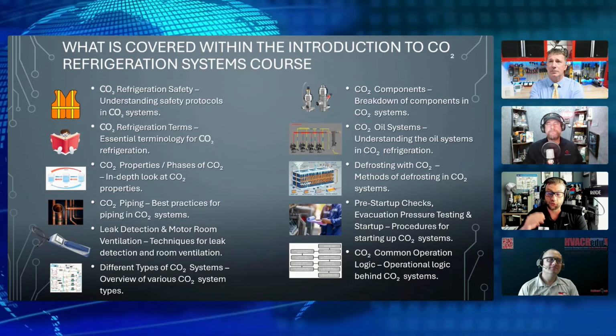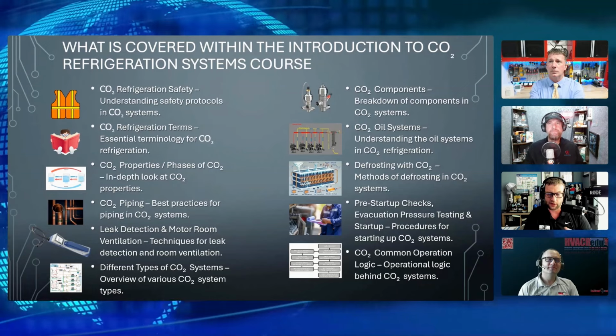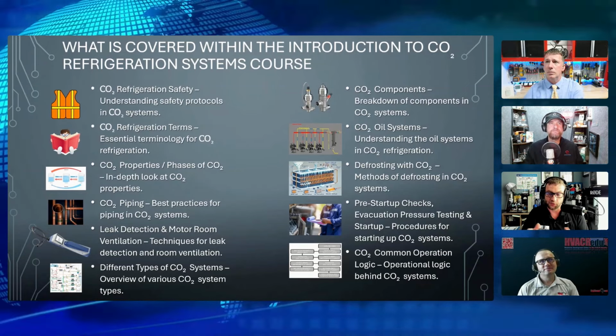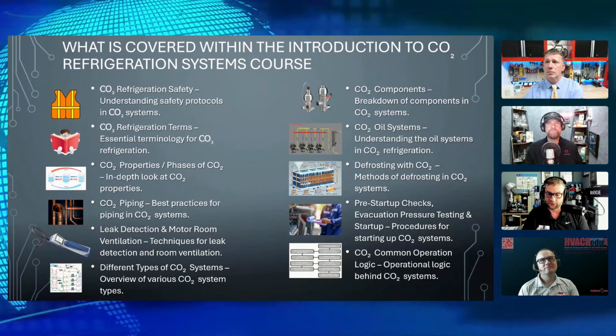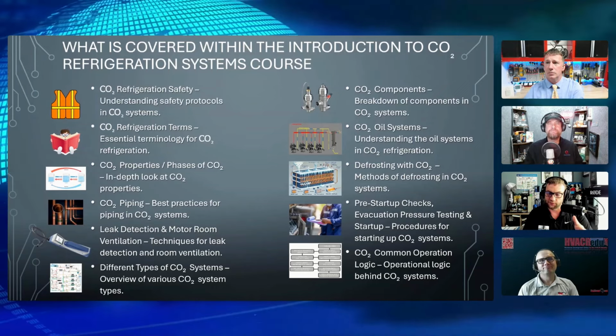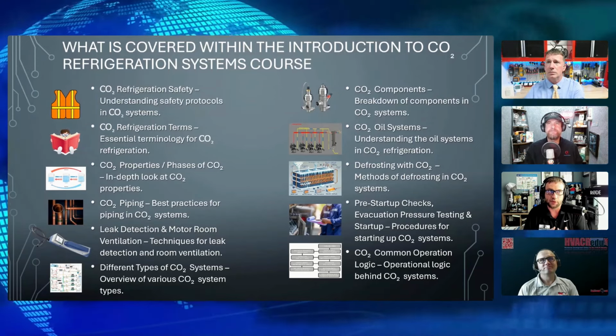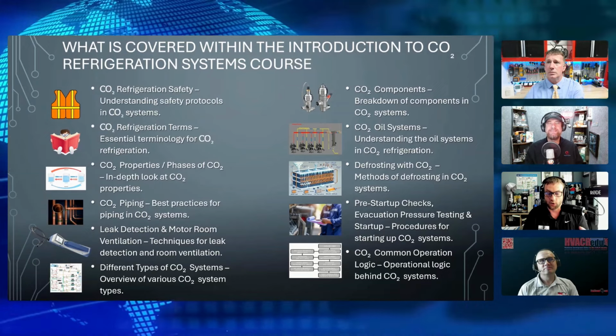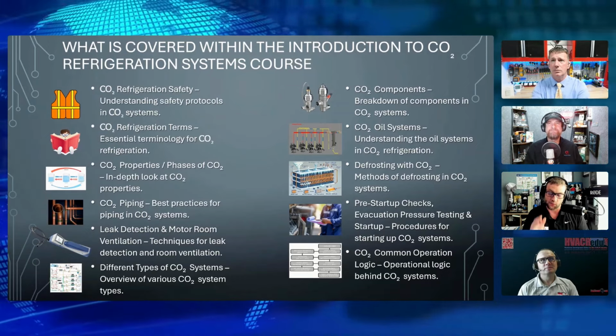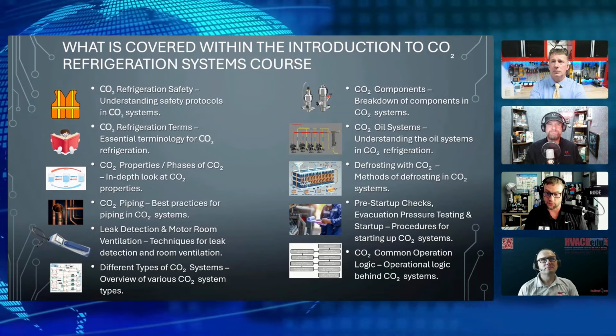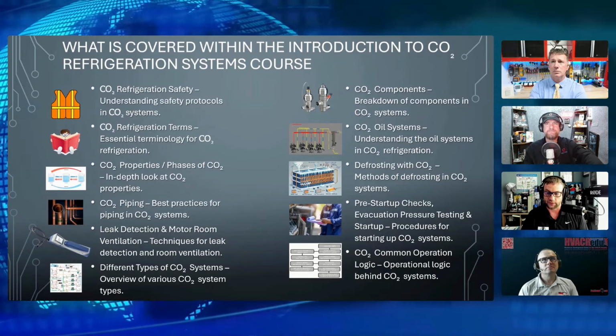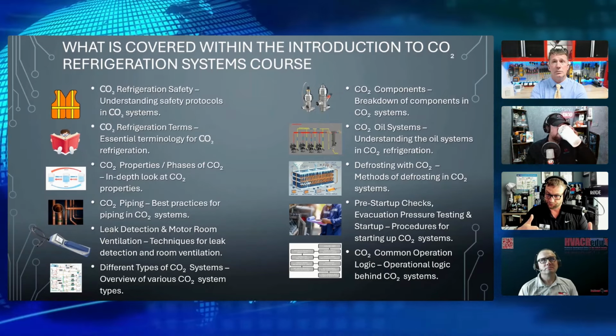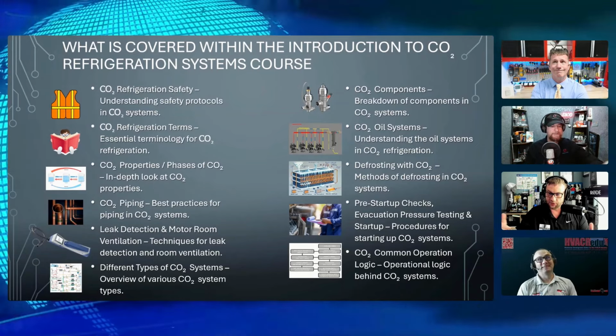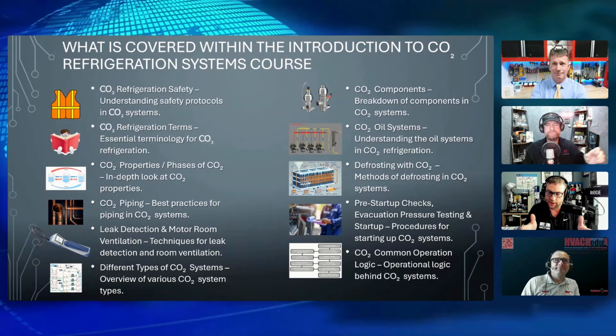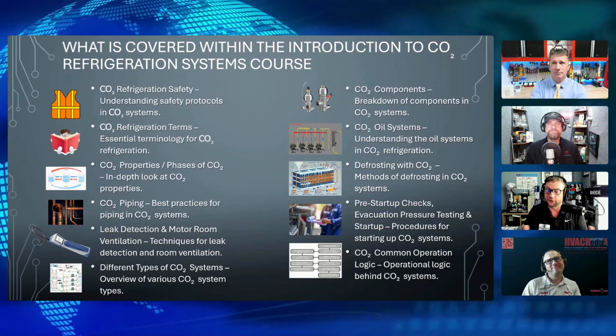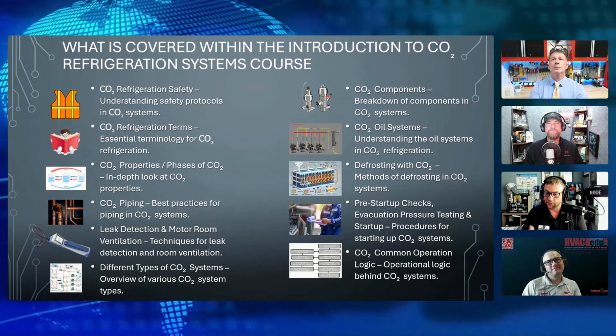So the way the piping is, which I didn't really discuss the other parts of the piping, this is in the component section, but we have check valves on a lot of the systems, so flow can't go backwards. So theoretically, if you have a leak, I want to say 100% of these circuits, as of right now, work off electronic expansion valves. So if they sense a leak, they will get a shutdown signal going to the case controller and say, hey, stop feeding refrigerant. So no refrigerant can go backwards, which is great now, because then it's basically going to trap what would be liquid or vapor in there, so it doesn't just keep pumping vapor CO2 within the system.